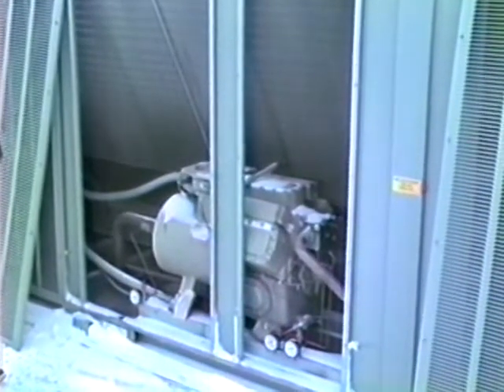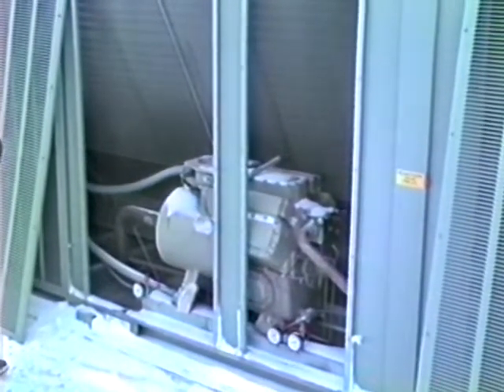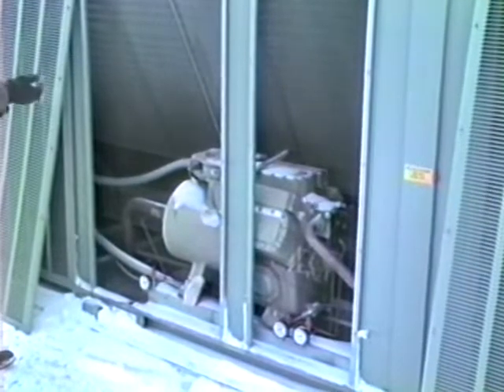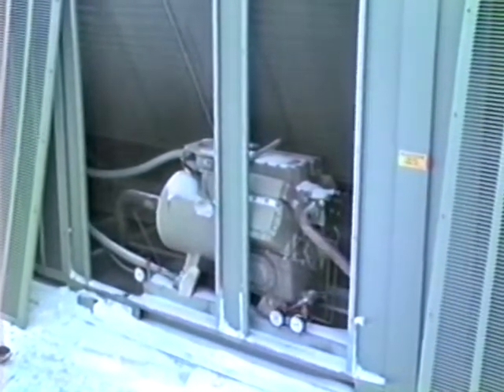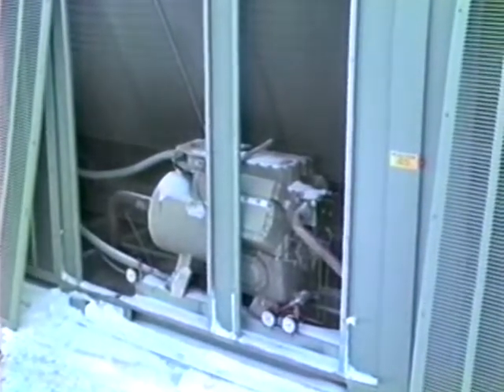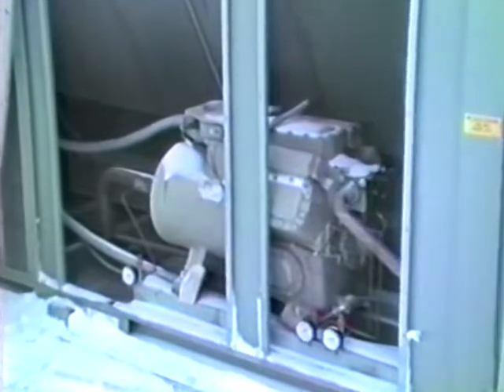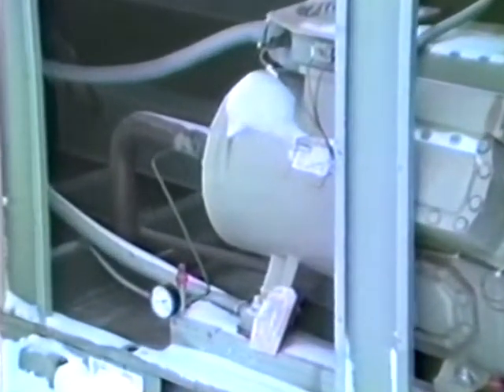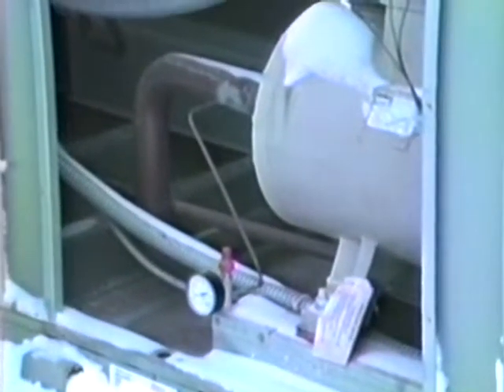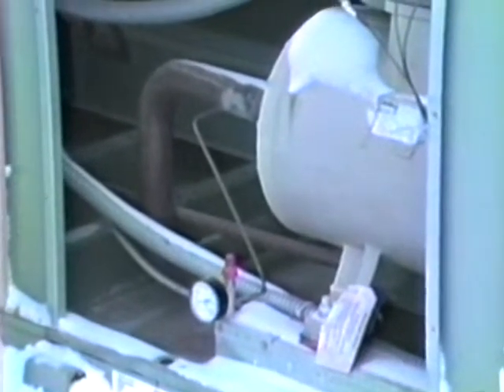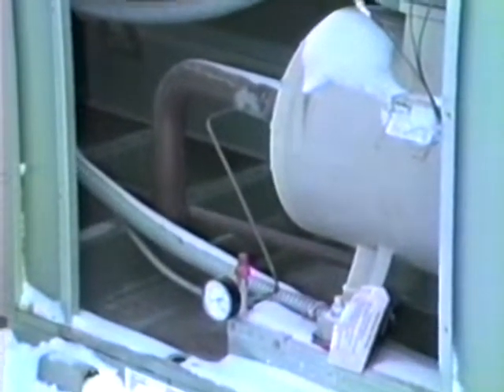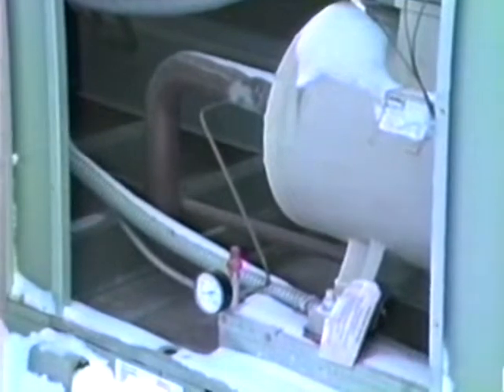As we mentioned before, there's 2 compressors. We want to look at now there's 3 gauges in here that we talked about for our maintenance routine inspections. The gauge on the left is the suction pressure gauge. In operation, the suction pressures normally should be somewhere between 55 and 70 pounds as read on the gauge.